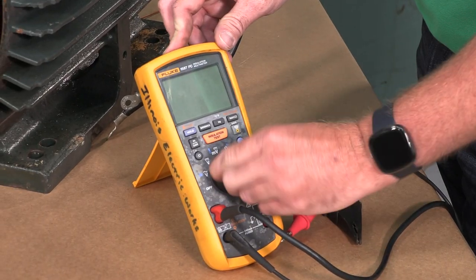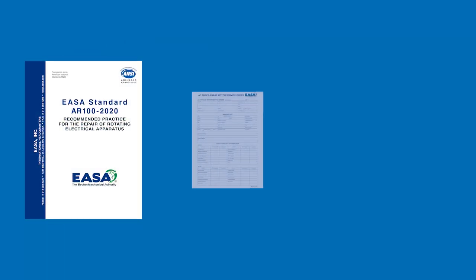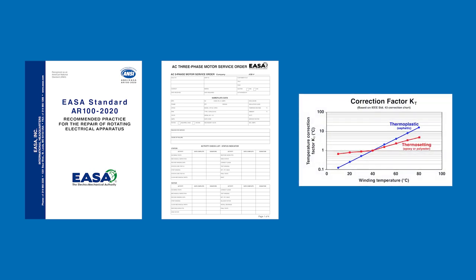To perform an IR test, you'll need a few tools and supplies: a megaohm meter, a thermometer, a cell phone or a stopwatch, the ANSI EASA AR100 standard, EASA's AC three-phase motor service order form or the form used by your service center, and the IEEE 43 correction factor KT chart.